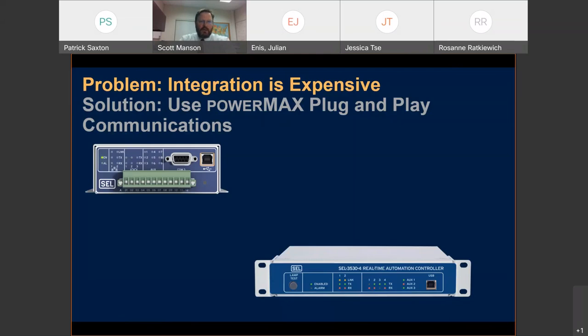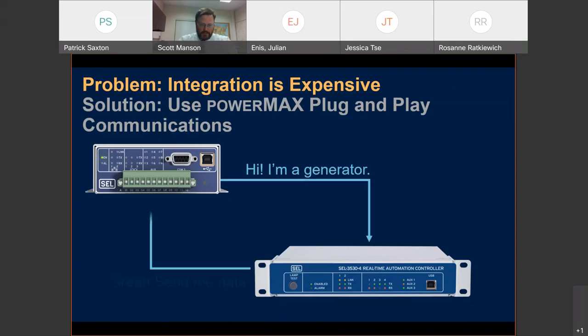The primary tool we're using is a protocol called DDS, Data Distribution Service, used by those in the world that put a premium on resiliency for many decades now. Therefore, it's a trusted protocol and a trusted mechanism. And it's a publish-subscribe type protocol. Here's the way it works. You put a small electronic device, ours is an RTAC, in a generator. And then here in the bottom right is the microgrid controller. When you add the generator, it publishes who it is and what its role can be to the microgrid controller. The microgrid controller automatically then responds back with a request for data and a set point.